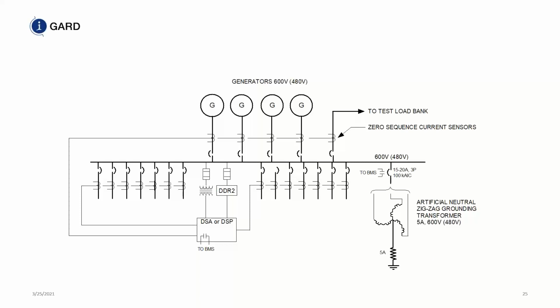So what we've done is we've employed a zigzag transformer on this bus, and you can put a small resistor on each generator, limit the fault current to 5 amps, so it doesn't matter which particular or how many generators you have online, you always limit the fault current to 5 amps. Now you can put pulsing on here, and you can actually enjoy the benefit of having an arc flash mitigation technique, not trip when you have a ground fault, and continue operation when you have a fault.